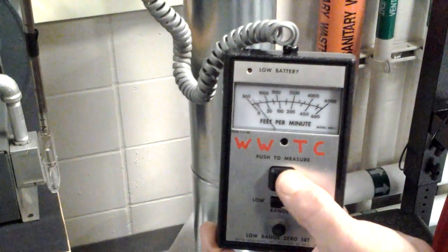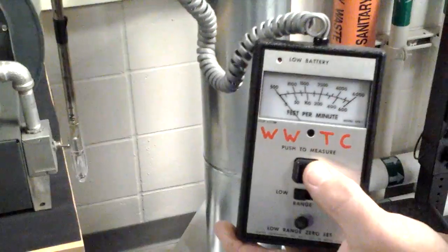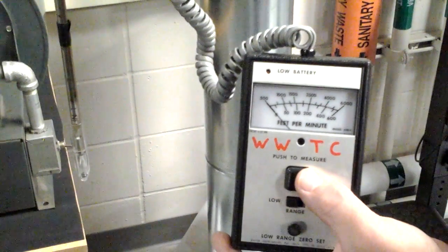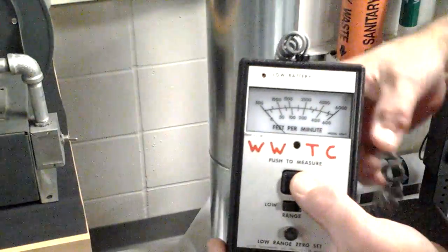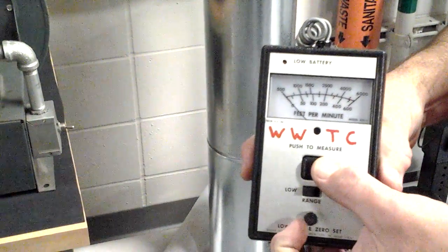Adjust the mechanical zero screw slot located just below the meter and position the pointer at 0 feet per minute, using the non-magnetic plastic adjustment tool provided.